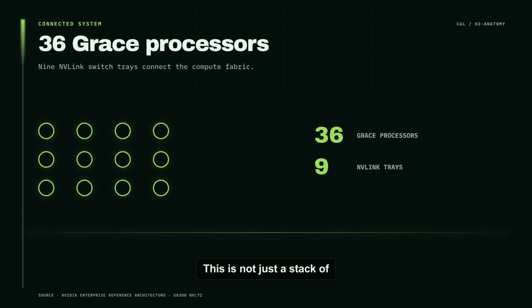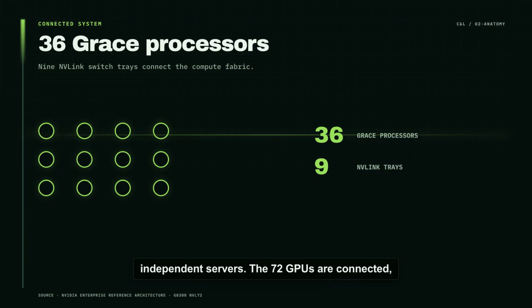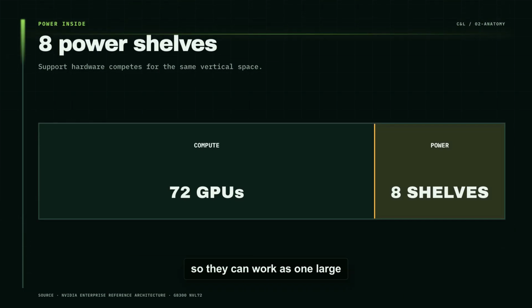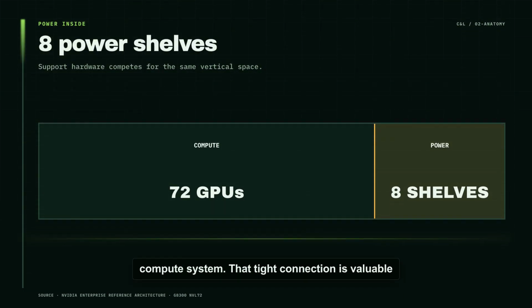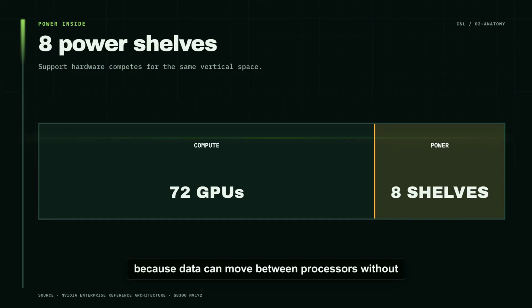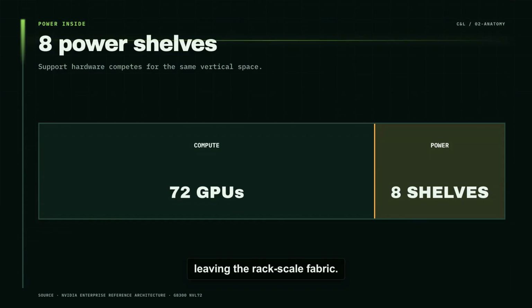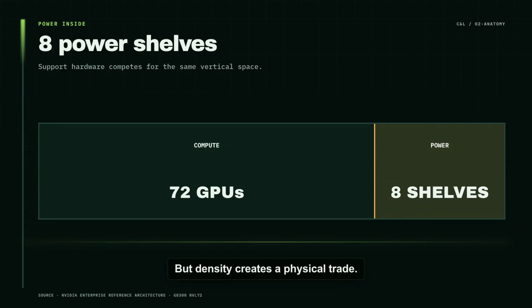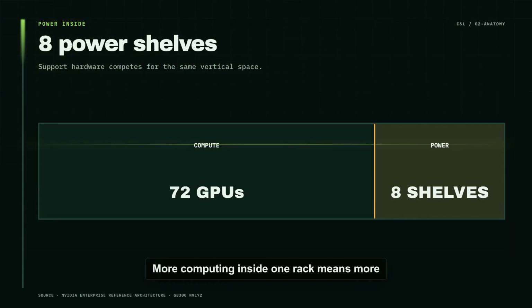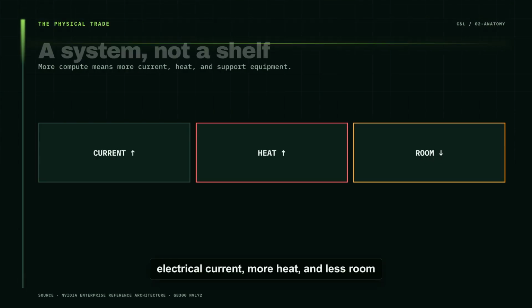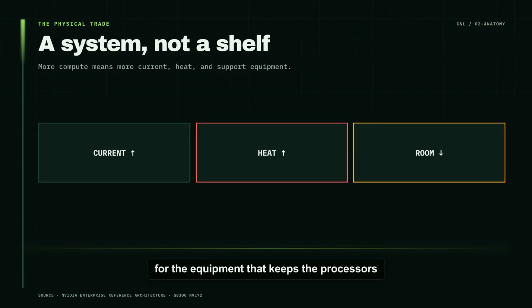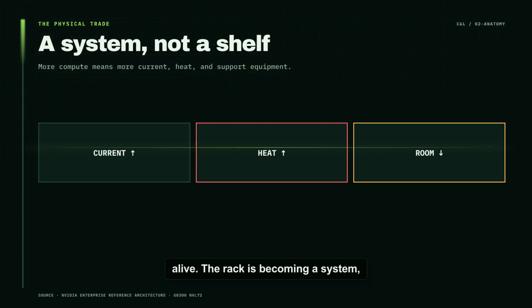This is not just a stack of independent servers. The 72 GPUs are connected so they can work as one large compute system. That tight connection is valuable because data can move between processors without leaving the rack-scale fabric. But density creates a physical trade. More computing inside one rack means more electrical current, more heat, and less room for the equipment that keeps the processors alive. The rack is becoming a system, not a shelf.